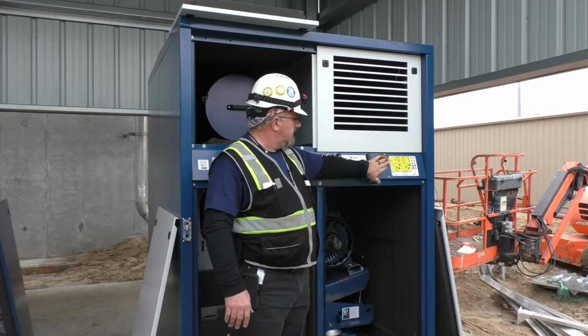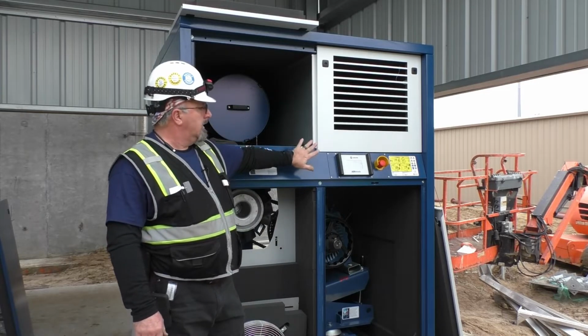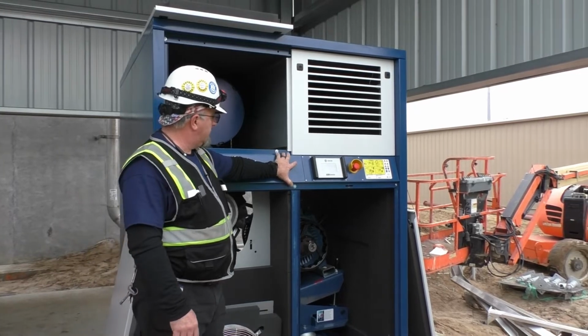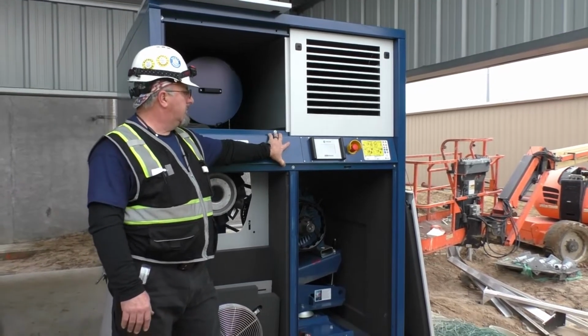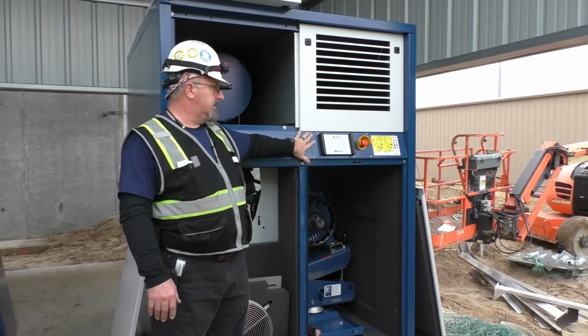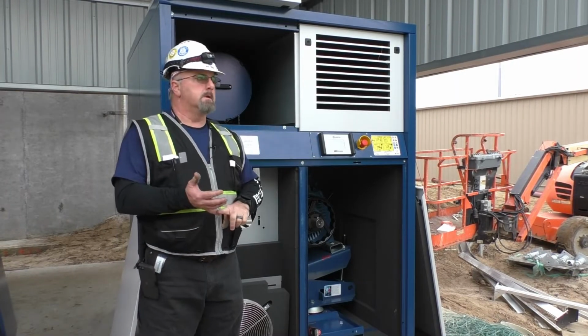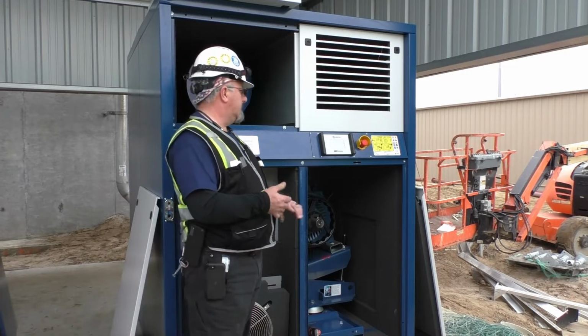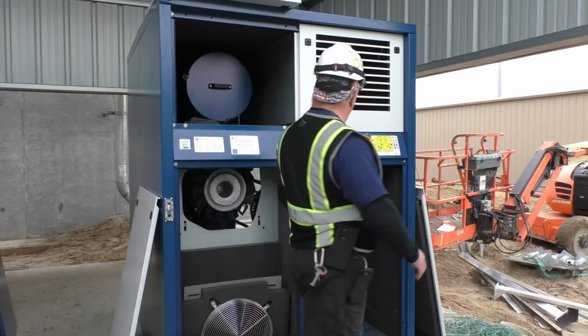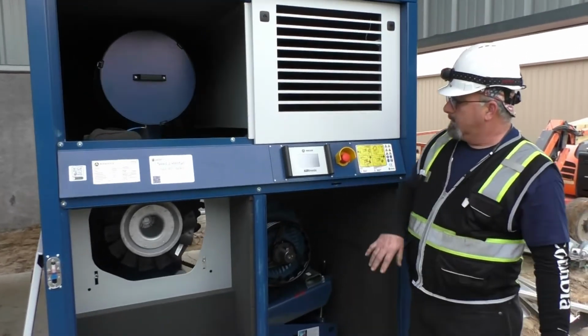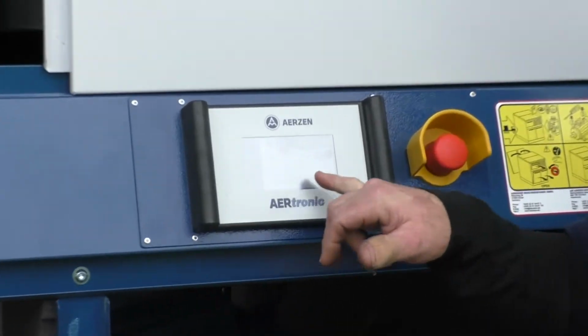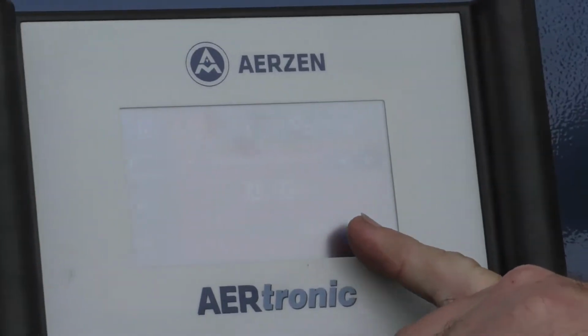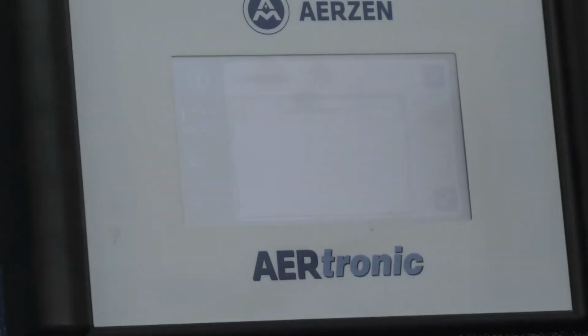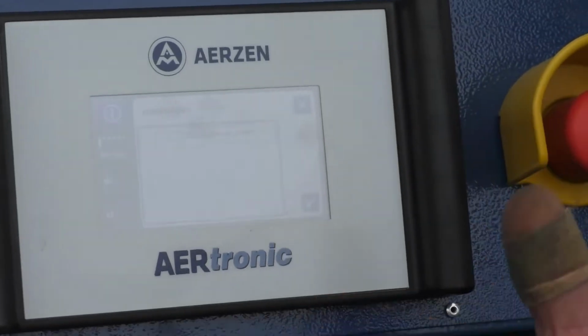You have the e-stop, which is part of the fault circuit for the blowers. Right now, as a temporary measure until SCADA is up and operational, there will be a fault connection between the blowers and the drives, so if there is a fault, it will shut it down. In that scenario, you'll have to come out here. I'll create a fault so it can be seen. By hitting the e-stop, that created a fault. Now with an active fault, this flash is red. There's a button up here in the top left corner. If I hit that, it takes me to the fault screen. That'll tell me what the fault is, so I know what I need to look at.